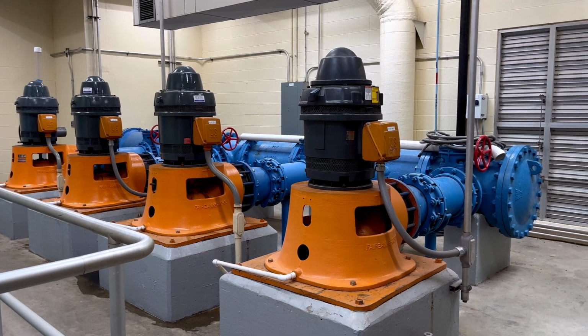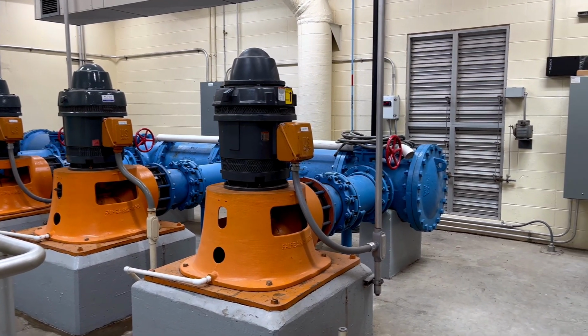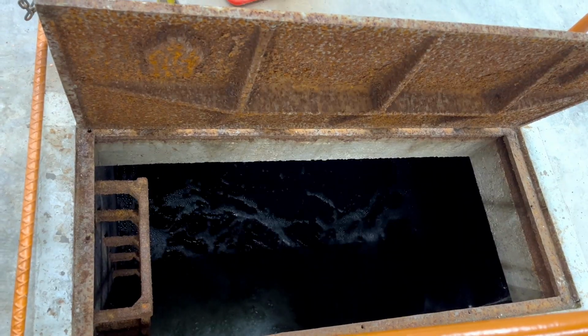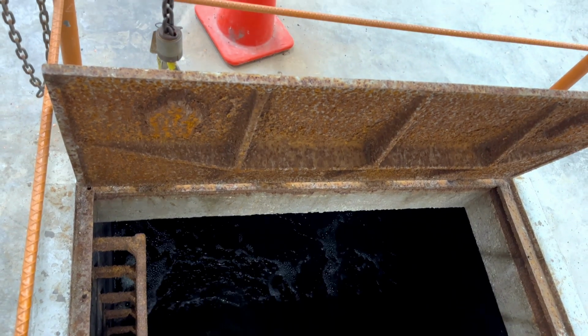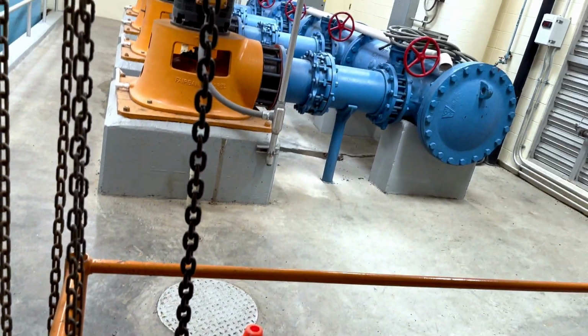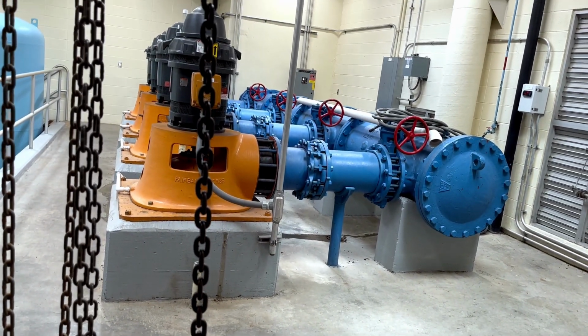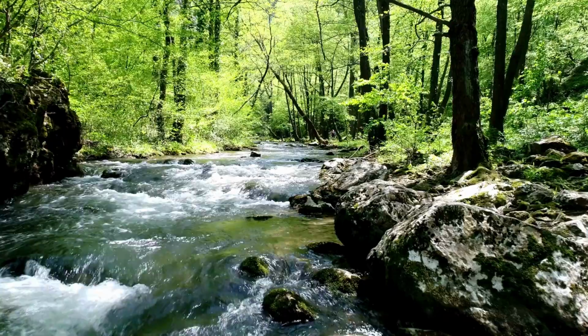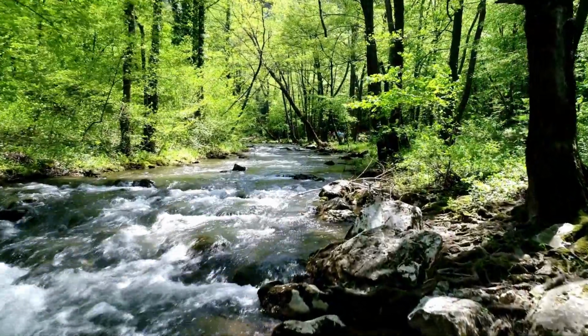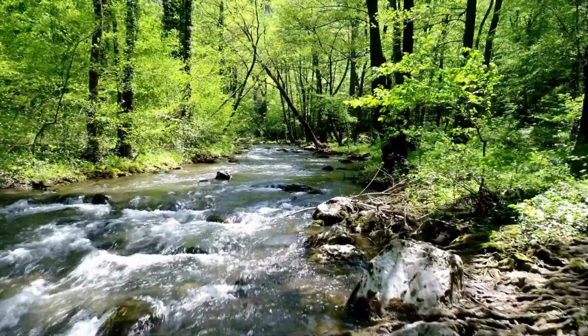The water then enters the final stage of the treatment process, the effluent outfall. Beginning in the effluent building where the flow rate is measured, the water cascades to capture air so that it will contain enough dissolved oxygen to meet or exceed the permit limit as it goes to the Cottonwood River. This is to help the water from the plant raise the oxygen concentration in the stream, helping aquatic life in the river to thrive.